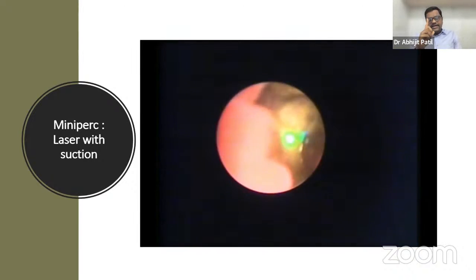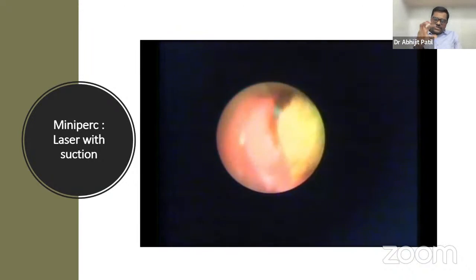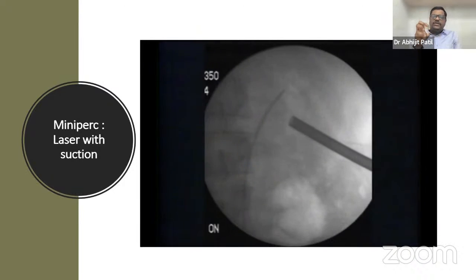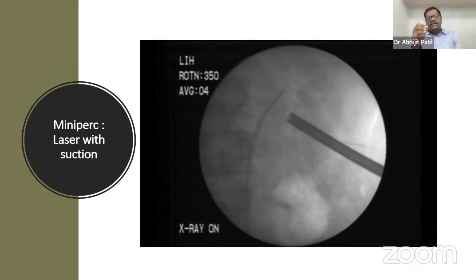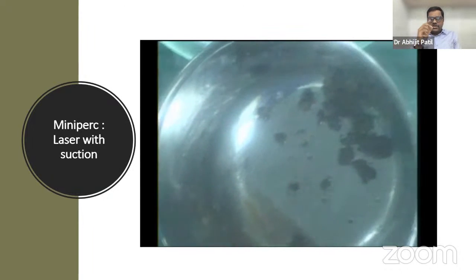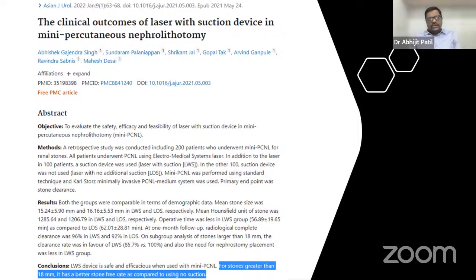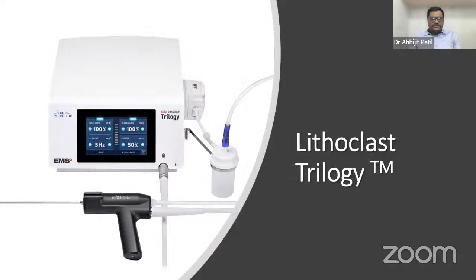The second thing is that this suction keeps the fragment near to your scope, and that is why you can disintegrate very fast. So these are the two benefits of addition of suction to this probe. Now we have published the data of our outcomes of laser with suction device in mini PCNL, which has been recently accepted in a journal of urology. And we conclude that for stone greater than 18 mm, this device has better stone free rate as compared to the conventional device with no suction.